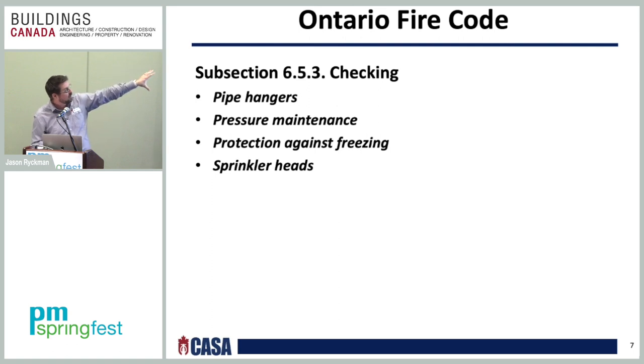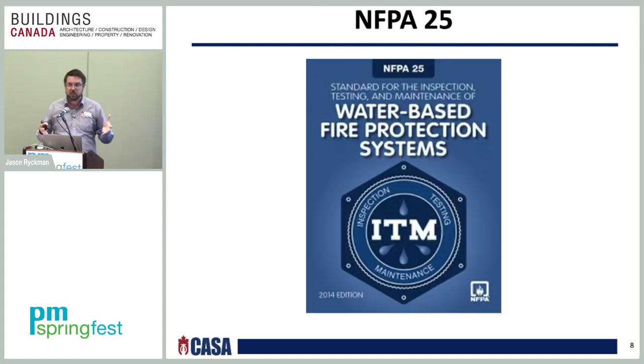Also, with the Ontario Fire Code, subsection 653 also stipulates checking, which is a requirement that you have to check your pipe hangers, pressure maintenance devices, which is on your dry systems, your protection against freezing and sprinkler heads. All these are in the fire code that you have to follow. And if you choose to do so, use the NFPA 25 document, which is what I'm really going to be discussing: the option of using NFPA 25.